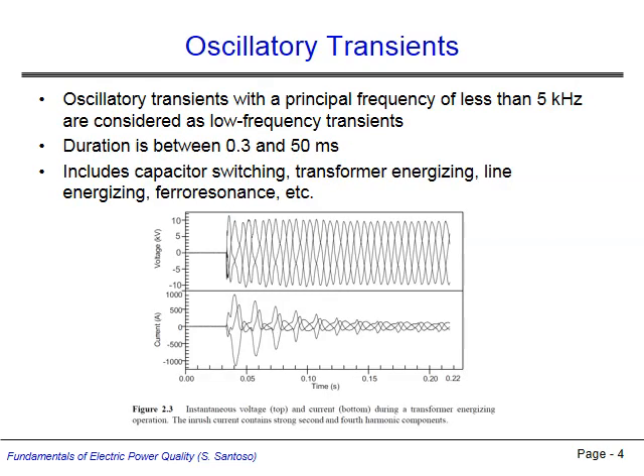Oscillatory transients are grouped by their principal frequency. If this frequency is less than 5 kHz, the transient is considered to be low frequency. Low frequency transients typically last between 0.3 and 50 ms and can be caused by phenomena such as capacitor switching, transformer energizing, line energizing, or ferroresonance. Shown in the figure is a low frequency transient caused by the energizing of a transformer occurring at about 35 ms.